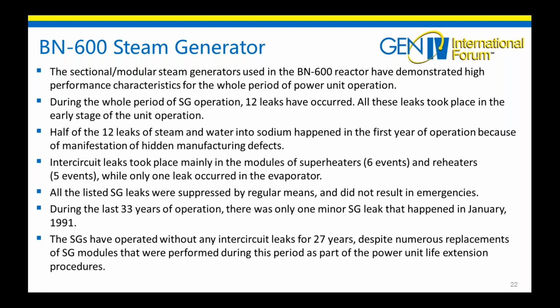Inter-circuit leaks took place mainly in the modules of superheaters, 6 events, and reheaters, 5 events, while only 1 leak occurred in the evaporator. All the listed steam generator leaks were suppressed by regular means and didn't result in emergencies. During the last 33 years of operation, there has been only 1 minor steam generator leak, which happened in 1991. The steam generators have operated without any inter-circuit leaks for 27 years, despite numerous replacements of steam generator modules that were performed during this period as part of the power unit life extension procedures.